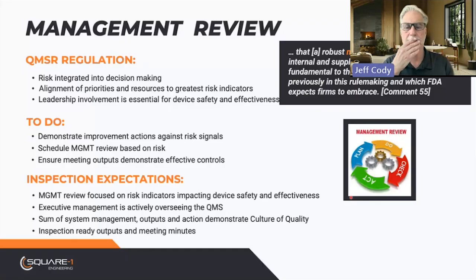Maybe just one comment in closing, particularly on the reoccurring. If there is reoccurrence after a corrective action, and maybe the effectiveness check was done and everything passed, but yet you start seeing complaints for something similar, that's an indicator that maybe a preventative action should have been taken in the CAPA. And that's something that's going to be looked for, right? Because if you get reoccurrences, that means you didn't necessarily get all the corrective actions. So this focus on preventative action, and when to use preventative action to prevent a future reoccurrence, is something that should really be weighed using risk, right, through your FMEAs and stuff like that. We have the tools, but it should really be a conscious, risk-based decision on whether or not we need to do the corrective and preventative action.